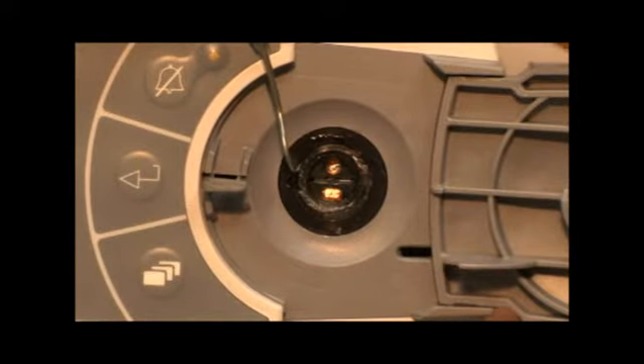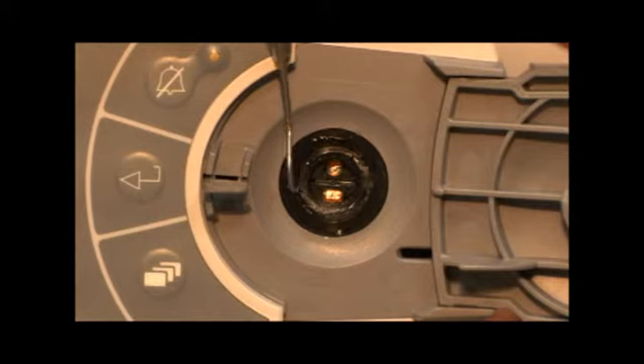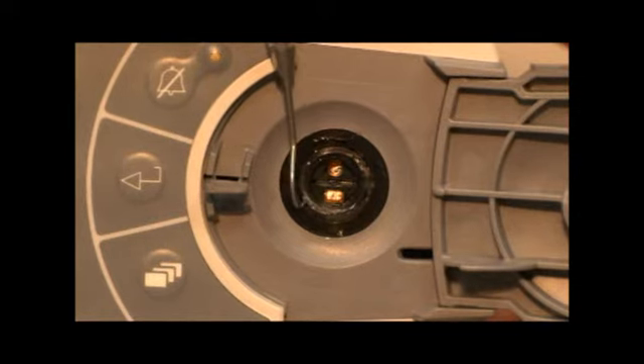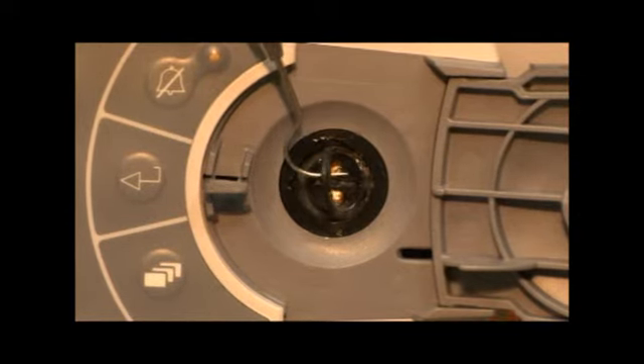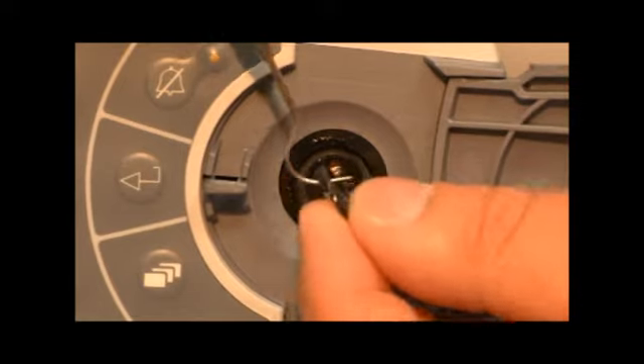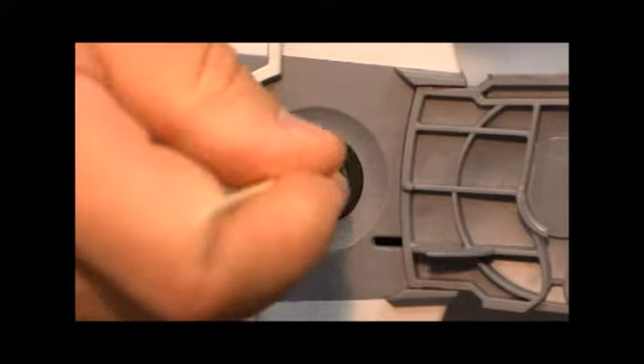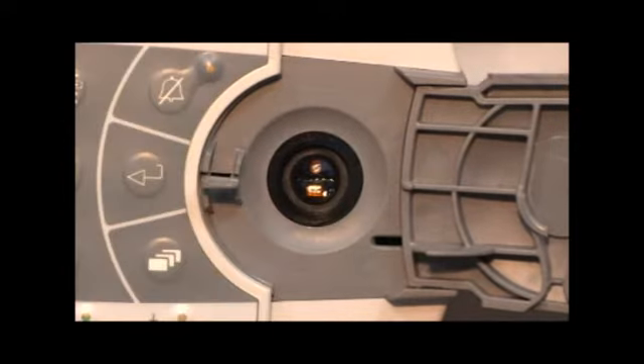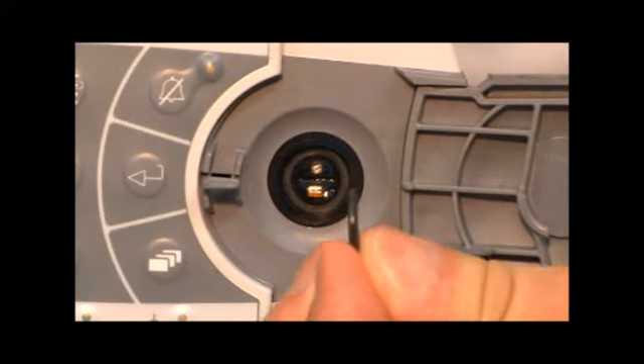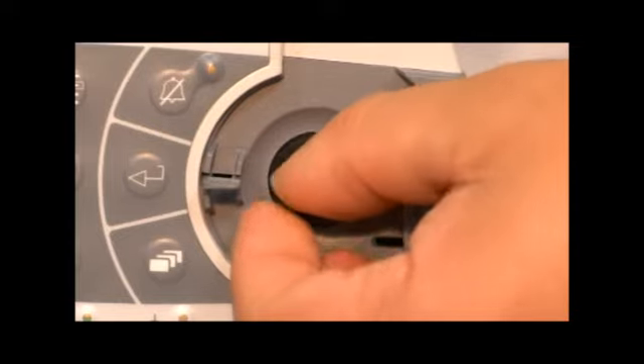for a thorough cleaning. To remove the gasket, use an O-ring pick or tweezers and carefully get under the gasket without scratching the docking surface. Then lift the gasket out. Note the gasket has a flat side and a beveled side. When replacing, the flat side goes in and the beveled side faces out. For ease of replacement, wipe the gasket gland with alcohol, then push the gasket in place with the cotton swab or blunt end of an O-ring pick.